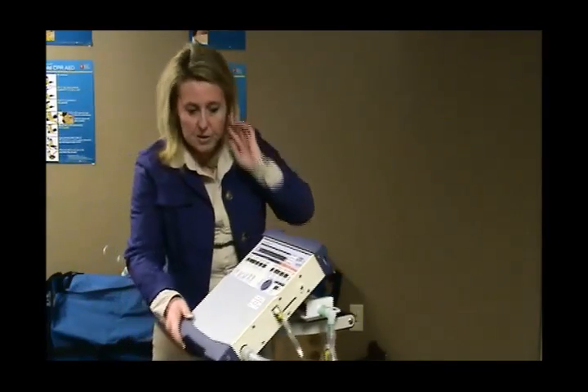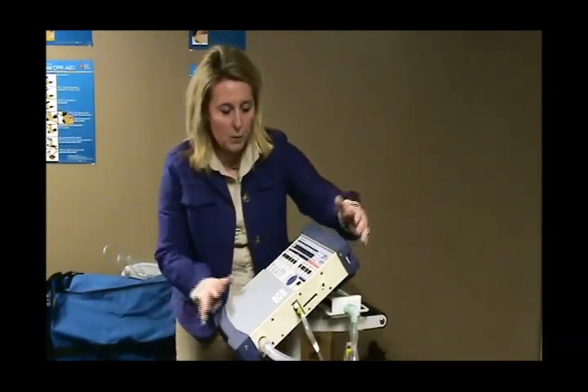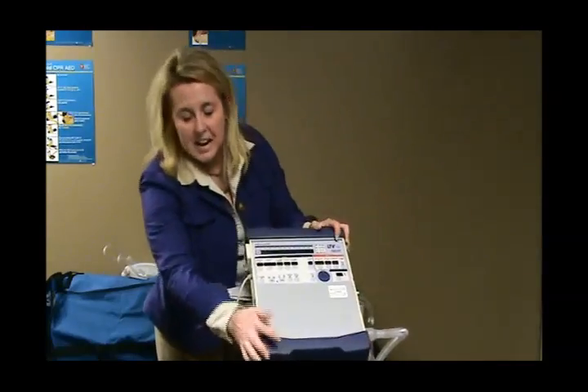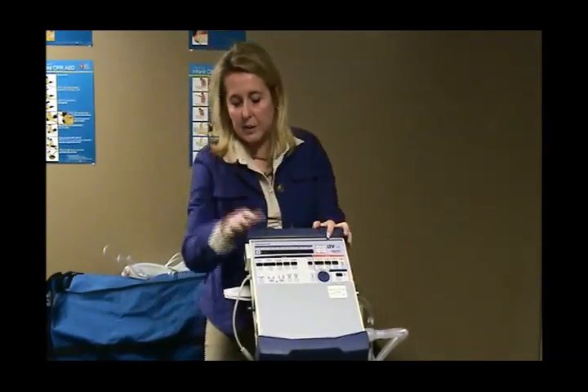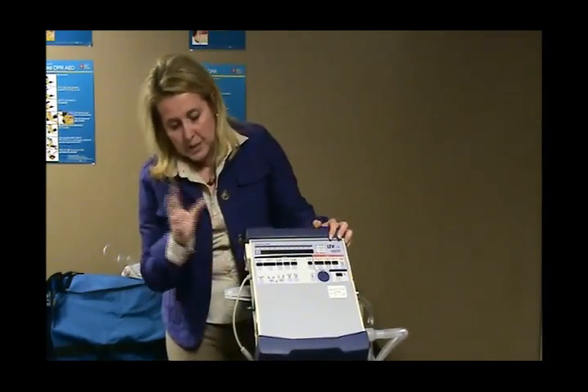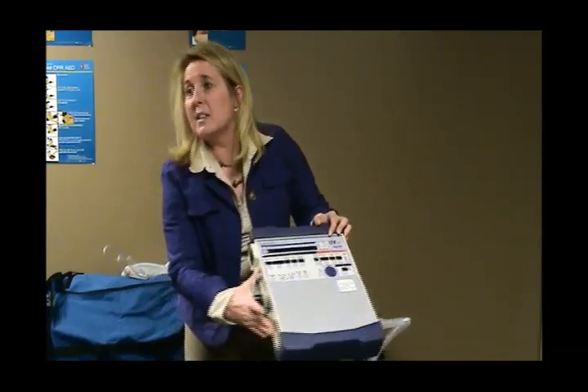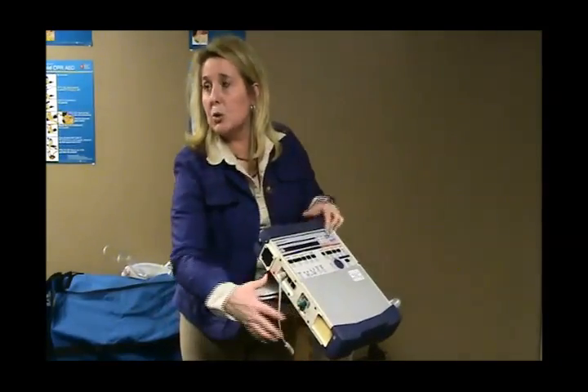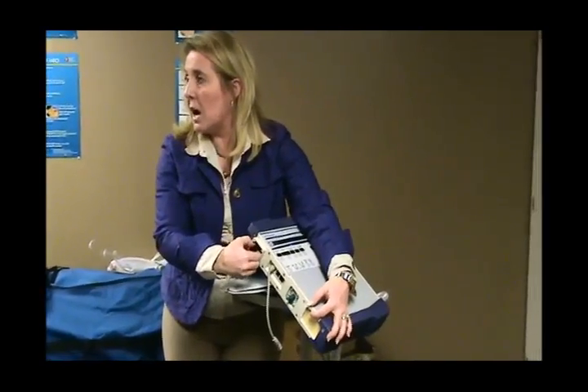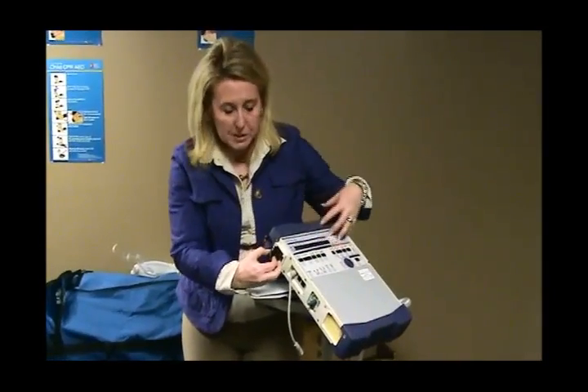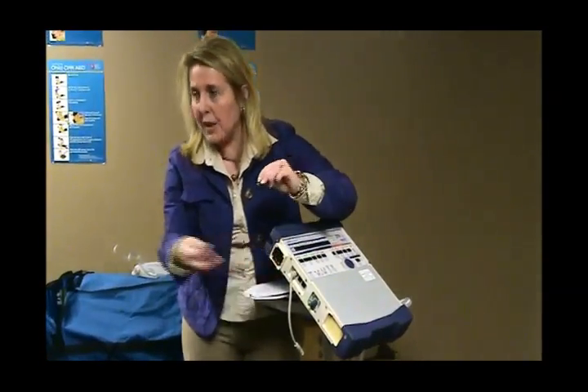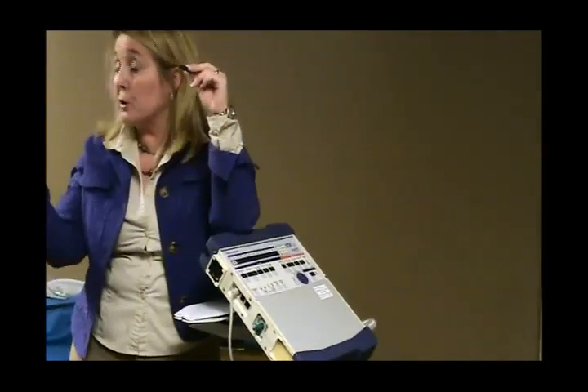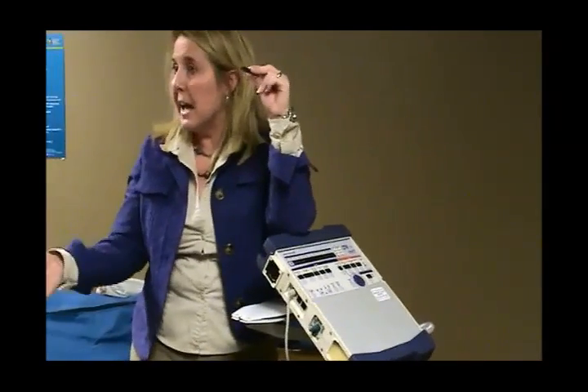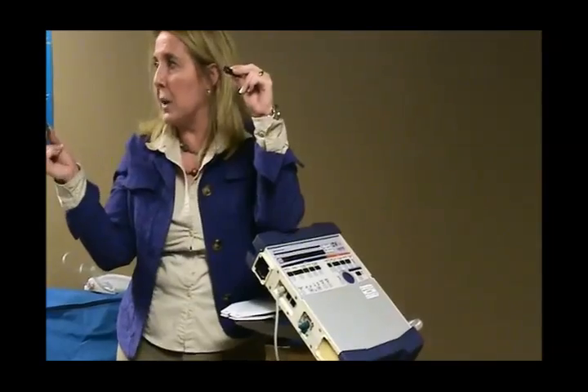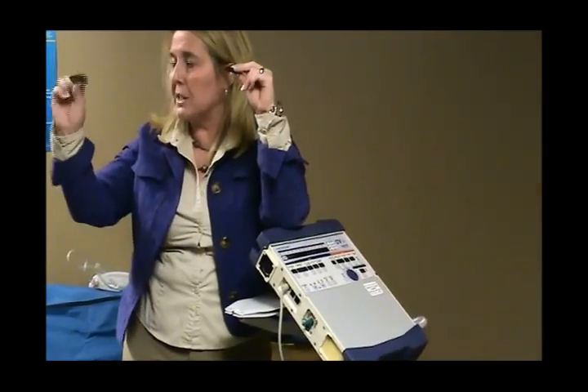I'm going to go ahead and turn the vent on. Well, first let's go on the outside and talk about the outside of the ventilator, and then we'll turn the vent on. There are 2 filters on the side of the vent that you will need to know to maintain. The first one is your fan filter that cools the electronics. You take this little thing off, you dust it off, or some people may say wash it off and let it air dry before you put it back in. Either way is fine, as long as it stays relatively clean.